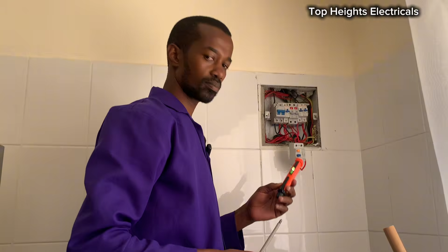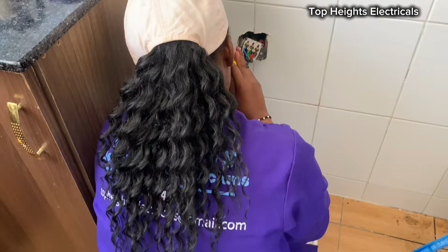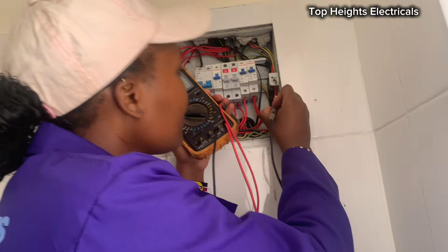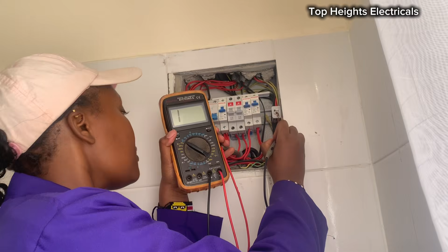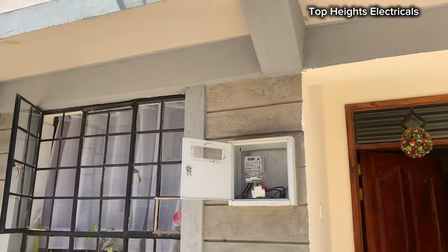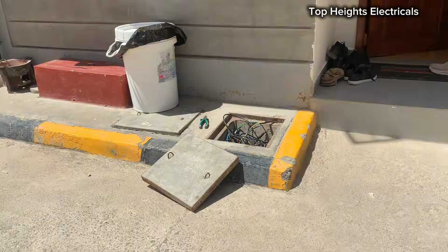We have connected this RCCB so that we can test whether each and every circuit will trip in case there is a fault. Having ruled out any possibility of an electric shock coming from the appliances or the internal wiring, we shifted our attention to the meter box, the earth pit, as well as the earthing that has been done to this house.